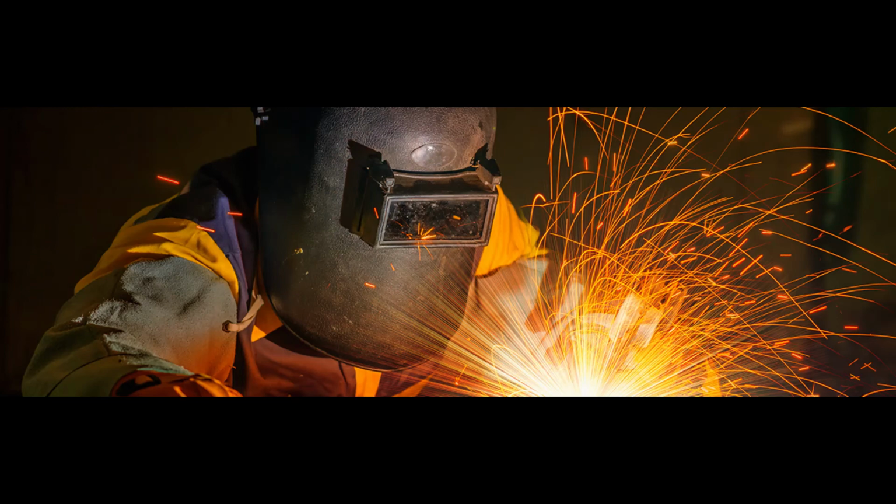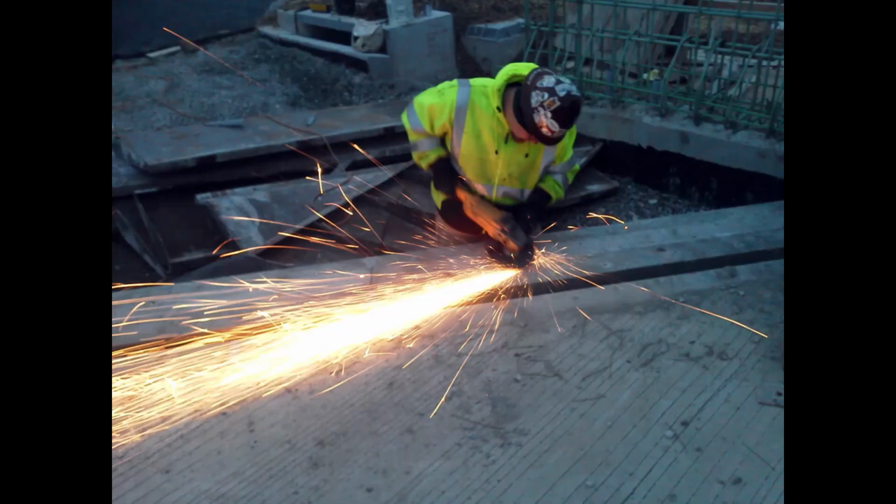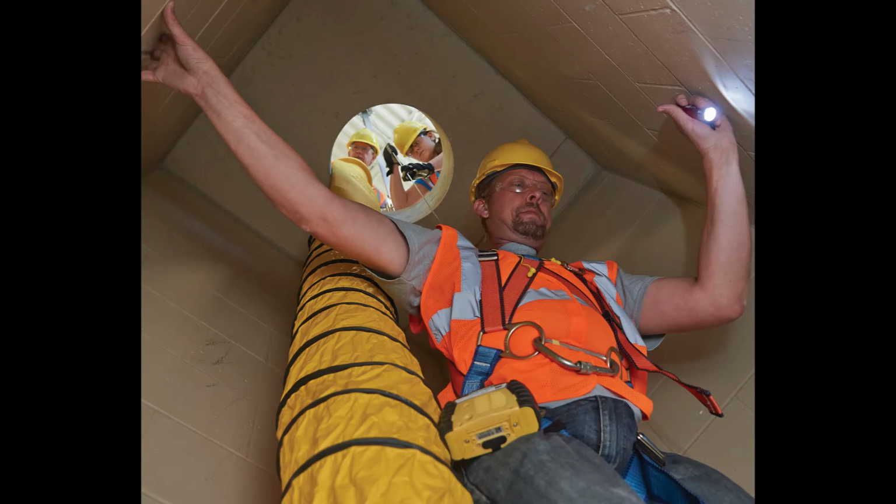And then there are some specialized precautions. In some cases, additional safety precautions are necessary. Areas to consider include, but are not limited to, piping. Prior to cutting or welding on pipes, the operator must ensure that the pipe is purged and empty. Proper ventilation is required in order to prevent inhalation of fumes such as hexavalent chrome. Then containers, they must be cleaned to ensure no flammable materials or vapors are present. Confined space is a whole different thing and much in addition to what we're talking about here.